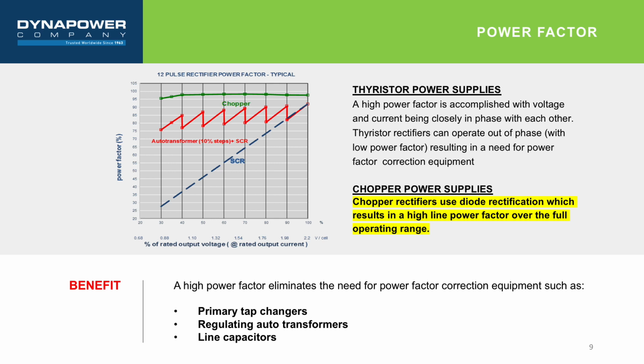Power factor. A high power factor results in voltage and current being closely in phase with each other. Phase-controlled supplies with retarded firing of the thyristors have inherently lower power factor. Typical thyristor rectifiers run at power factors in the range of 0.85. Primary tap changers, PF correction capacitors, or a regulating autotransformer may be used to improve the line power factor of thyristor rectifiers. Tap changers enable voltage regulation or phase shifting by varying the transformer ratio under load without interruption.